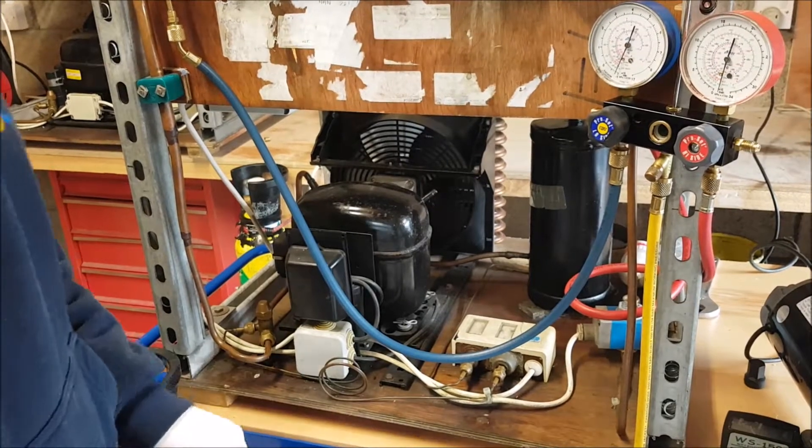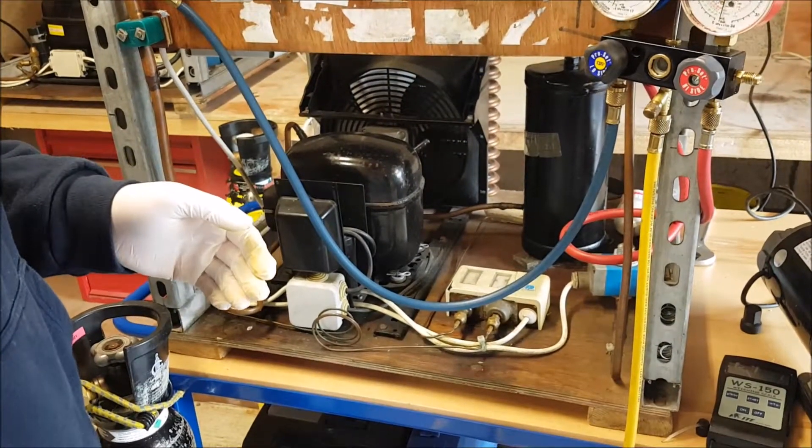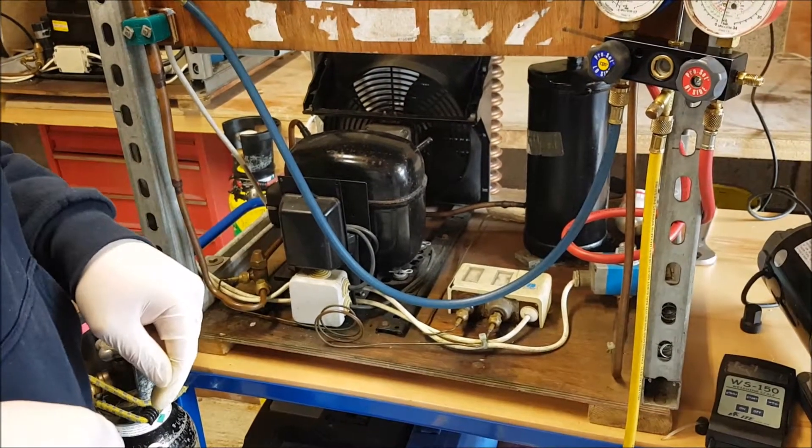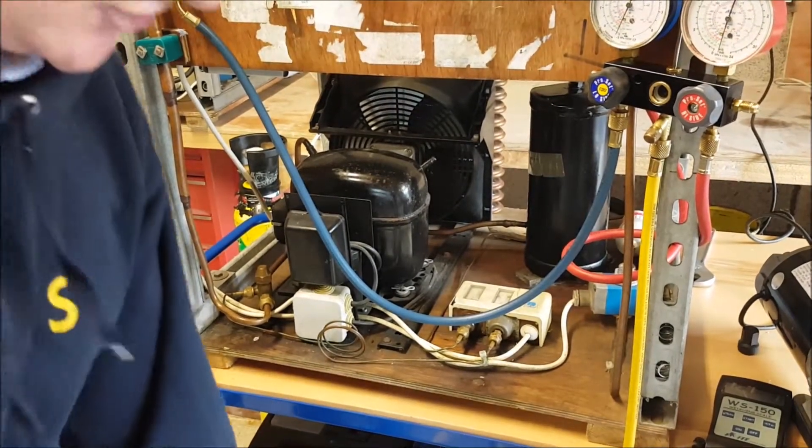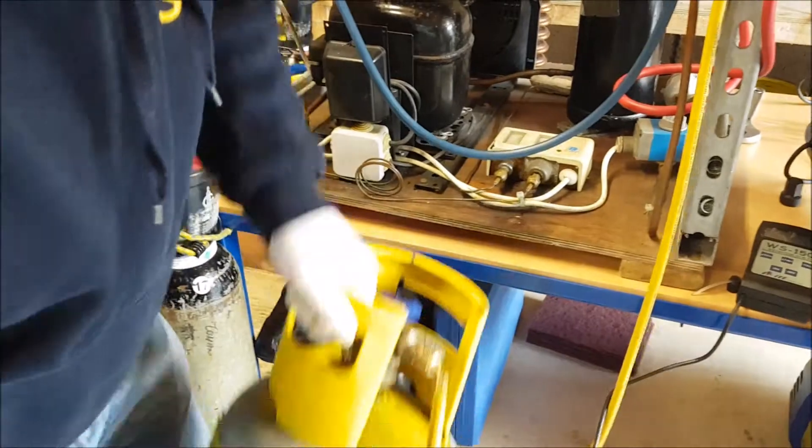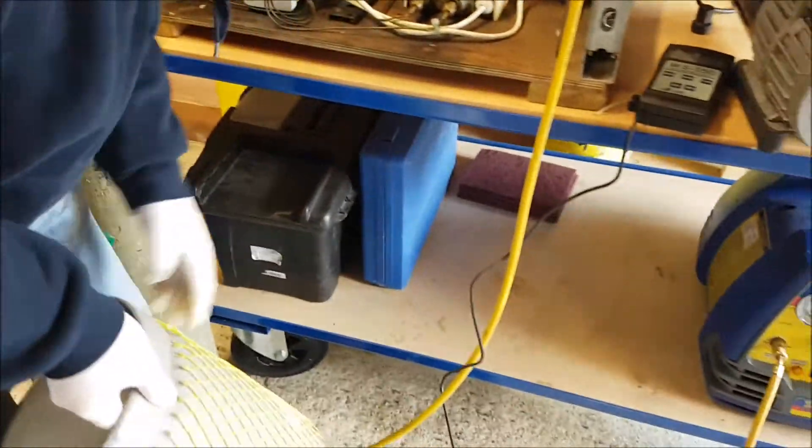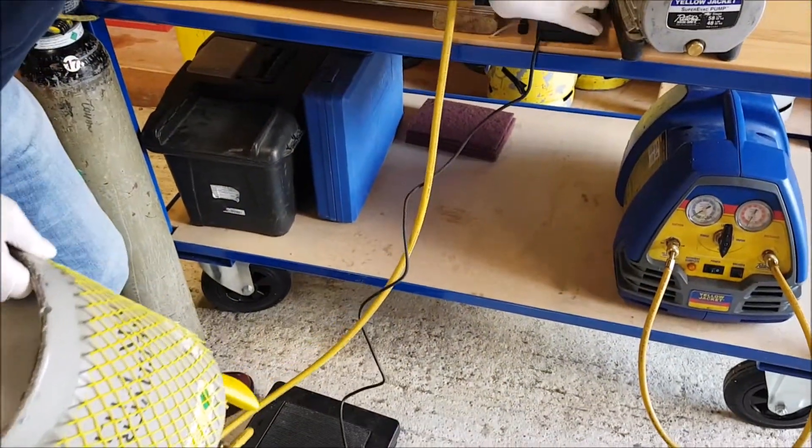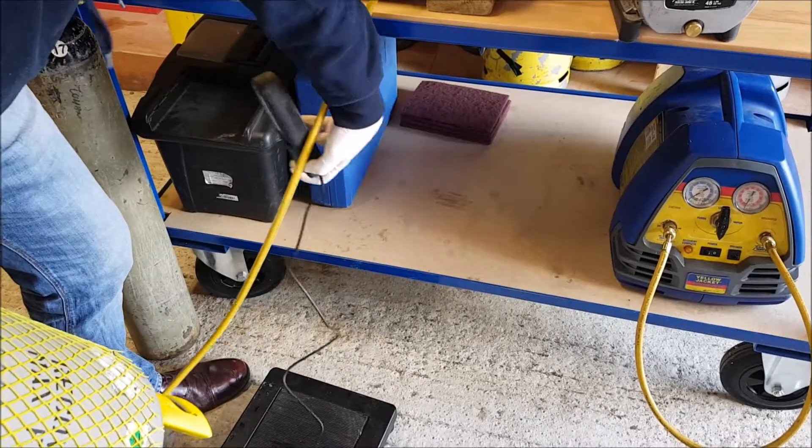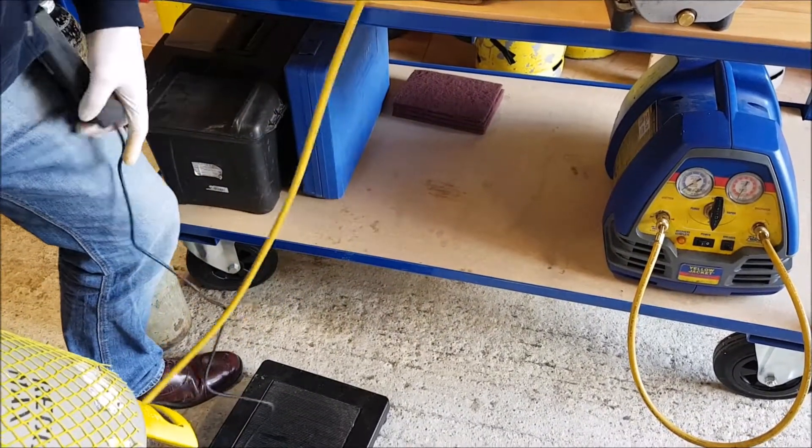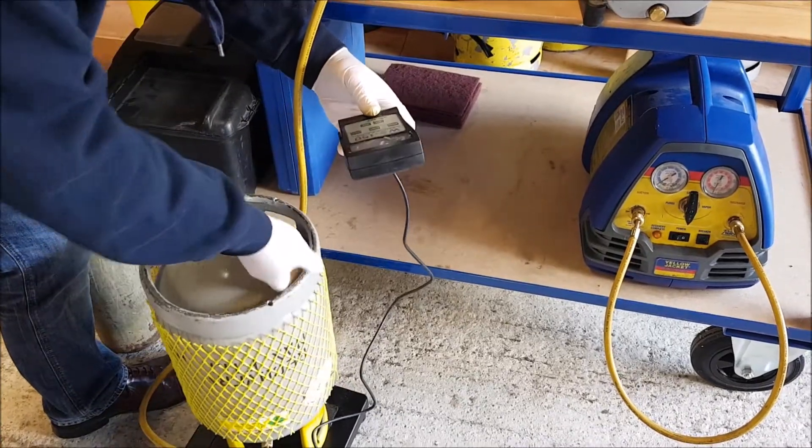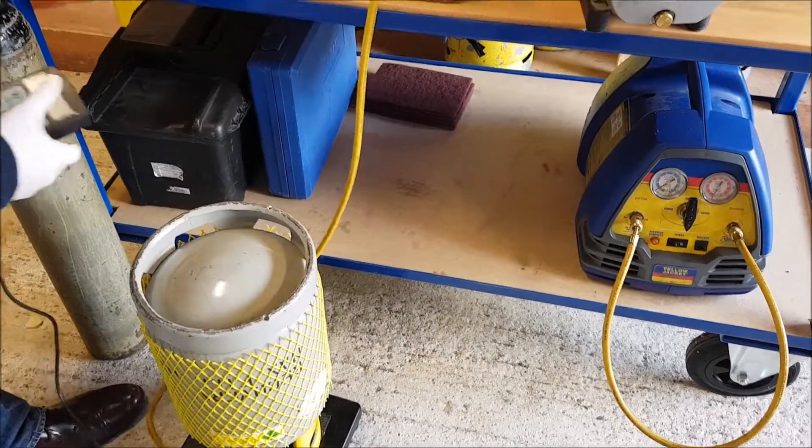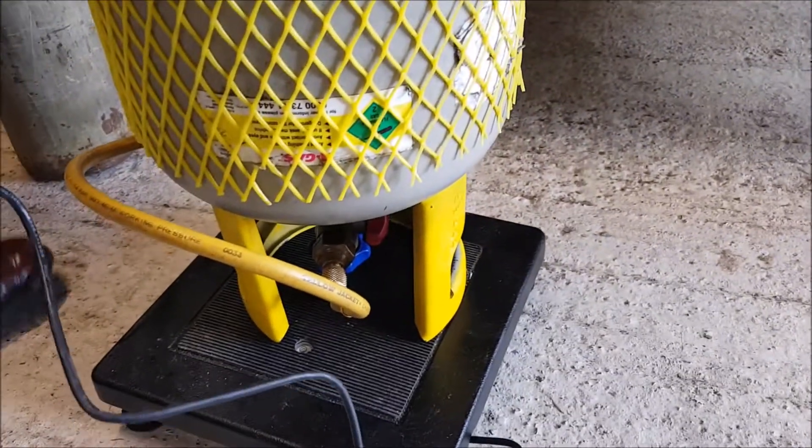That little purge was enough from my point of view. I'm happy that the system is free of air. Now the next thing I need to do is this is a zeotropic blend, it's 404a. You must liquid charge. In order for me to liquid charge in this particular bottle, I turn it upside down. By turning it upside down, my vapor port is now becoming a liquid port.